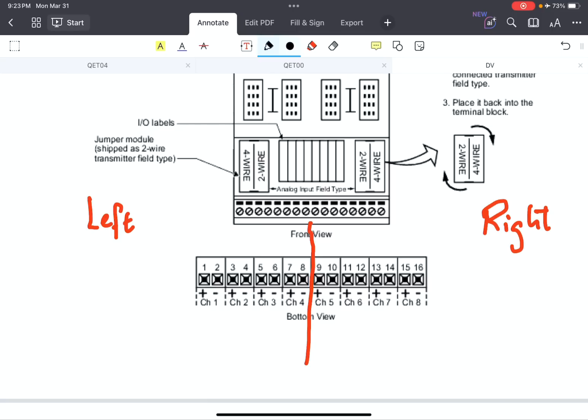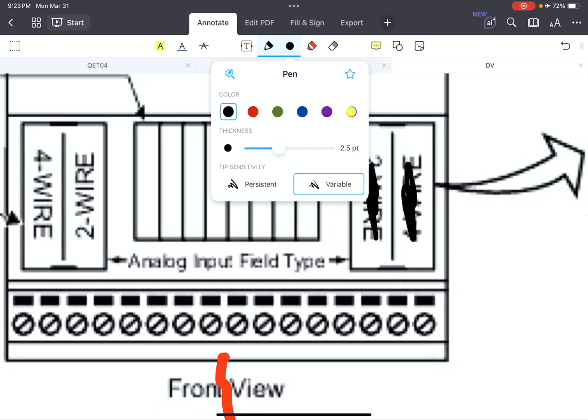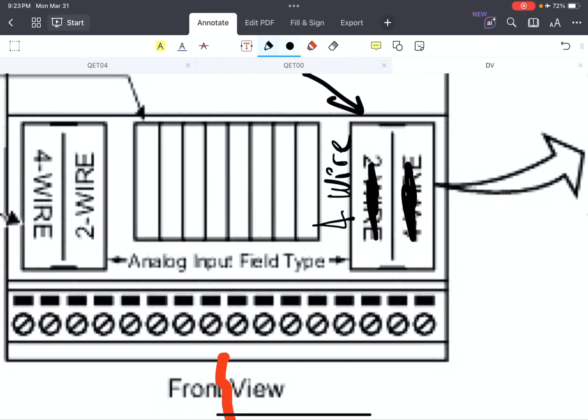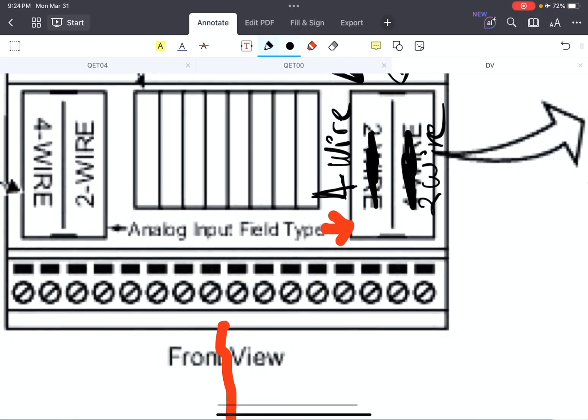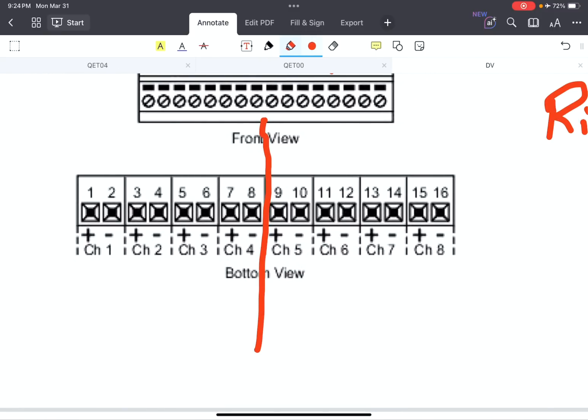For a four-wire configuration on the right side, you should remove this jumper and rotate it. If the arrow here is indicating to a value of 4, as is the case here, and the arrow is indicating to 4, you can install 4-wire transmitters.